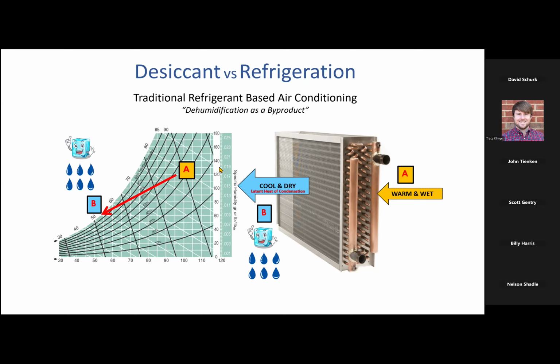Now, I'm saying around 130 grains per pound of moisture coming in. What does that mean? Well, that's pretty darn humid air. There are 7,000 grains in 1 pound of water. So what this is saying is for every pound of air, I have 130 seven-thousandths of a pound of moisture in that air. Doesn't seem like a lot, but we know it can wreak havoc on buildings if it isn't dehumidified properly. So I'm going to take that air from point A, I'm going to run it through my cold cooling coil, and I'm going to cool it down.